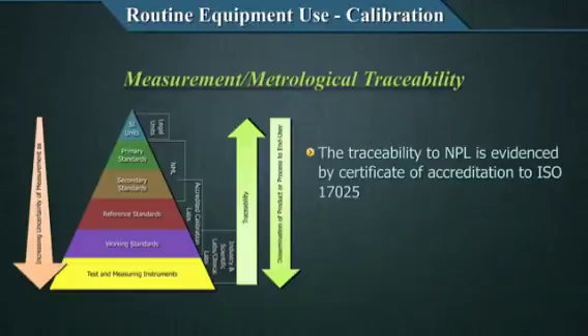In India, the traceability to NPL is evidenced by the certificate of accreditation to ISO 17025, and we'll talk about this again in later sections. The reference material you use in your lab, or those with which your external agencies calibrate your equipment, need to demonstrate this kind of traceability to ISO 17025. That is generally given in your calibration certificate. We'll show you an example later.